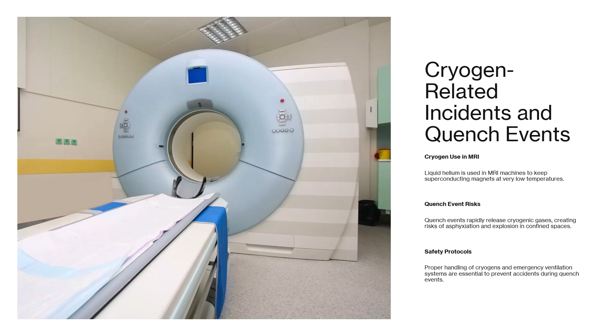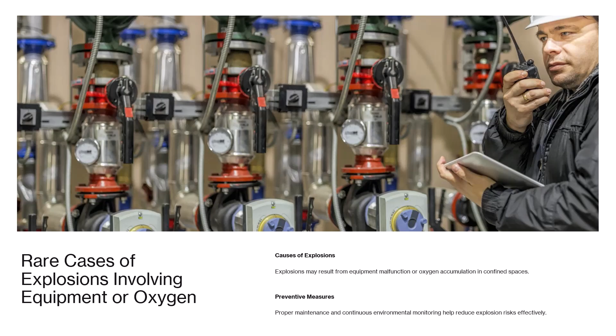MRI machines use cryogens like liquid helium to maintain superconducting magnets. Quench events release these gases rapidly, posing asphyxiation and explosion risks. Safety protocols must address cryogen handling and emergency ventilation. Though uncommon, explosions may occur due to equipment malfunction or oxygen accumulation. Proper maintenance and environmental monitoring are necessary to mitigate such hazards.